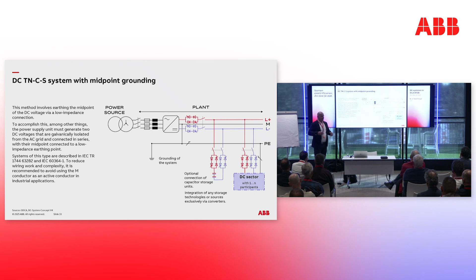That brings me to the next part, which is control. I said that typically the DC networks are voltage controlled, right? So how do we control this voltage, and what controls do we need? Depending on the size of the system, the control can get quite advanced and a little bit involved. When we have a really, really small system, think of a point-to-point connection, we need only this—I essentially have the loops inside of the converter, nothing else.